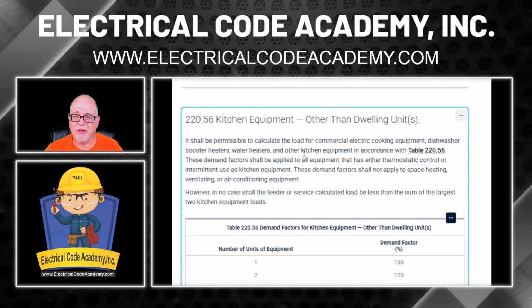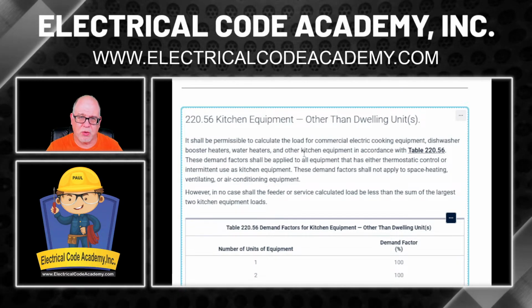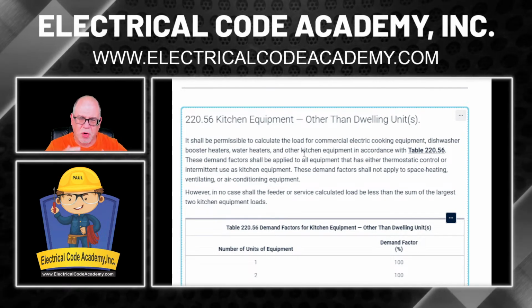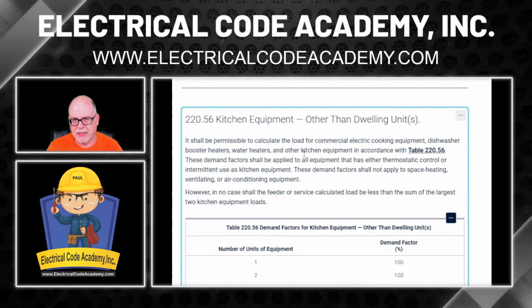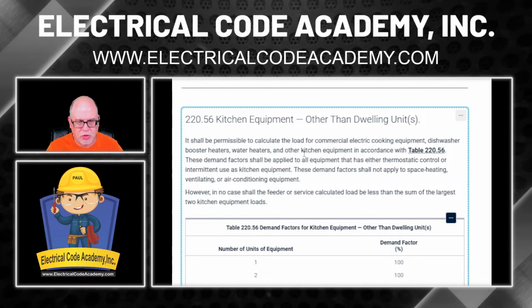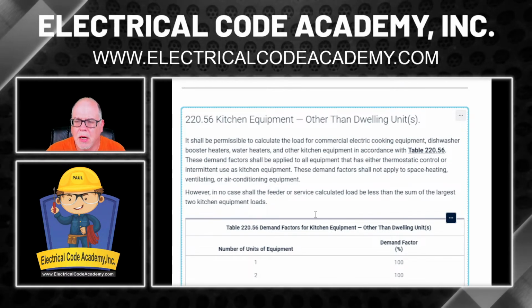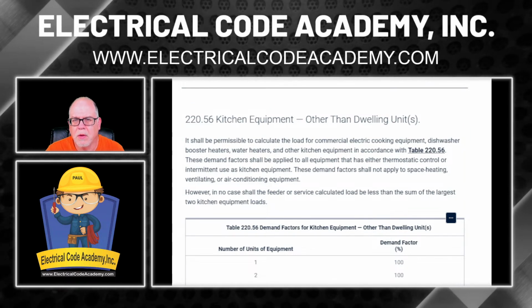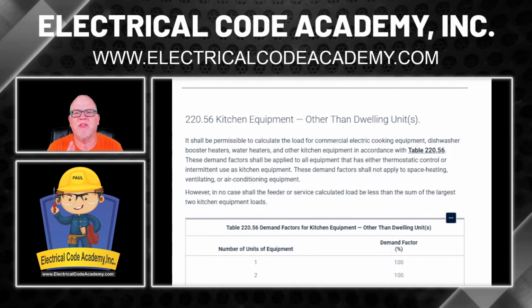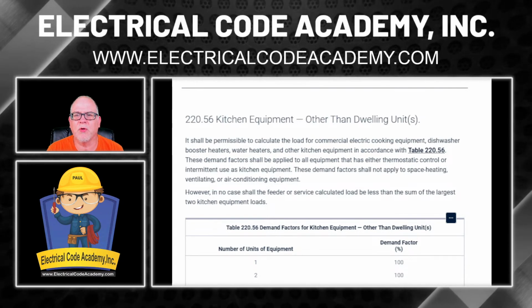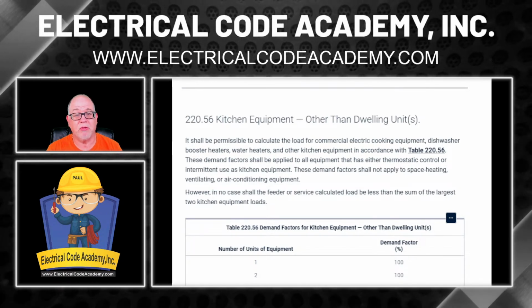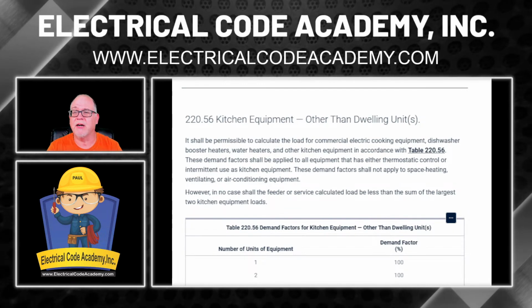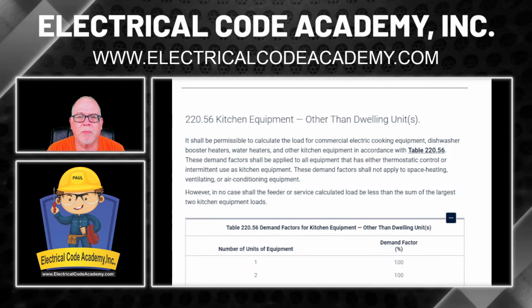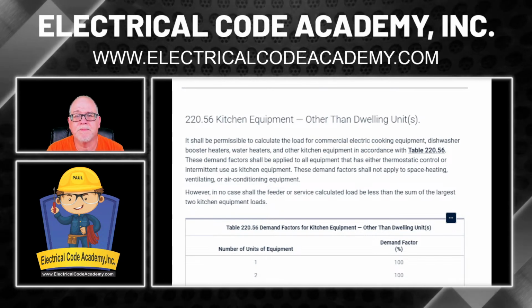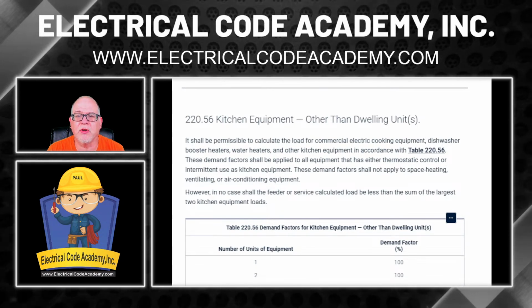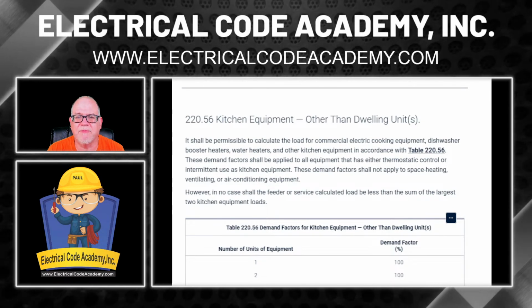All right. So this is like commercial electric cooking equipment. This is everything that's in like a commercial kitchen. That's what we're dealing with. So the contribution to the load for this kitchen is what we're working with. Let's read it. It says, it shall be permissible to calculate the load for commercial electric cooking equipment. Okay, so we do have cooking. We have ovens, so we're good there. Dishwasher booster heaters. We do have a booster heater. Water heaters and other kitchen equipment in accordance with table 220.56.